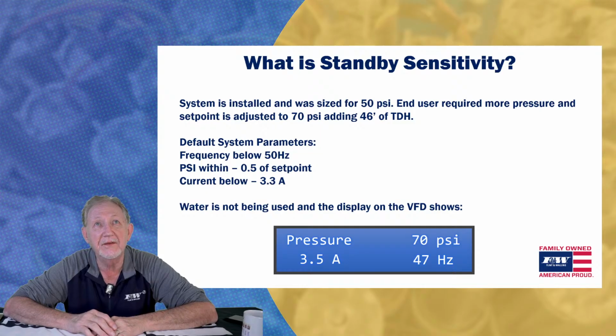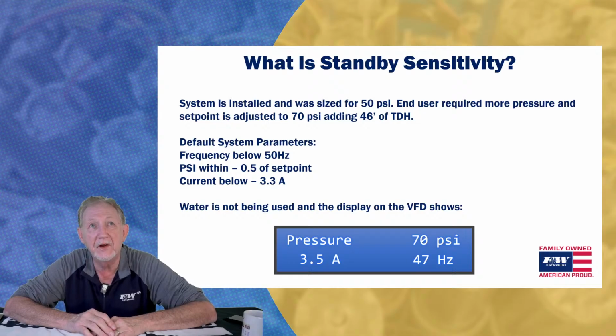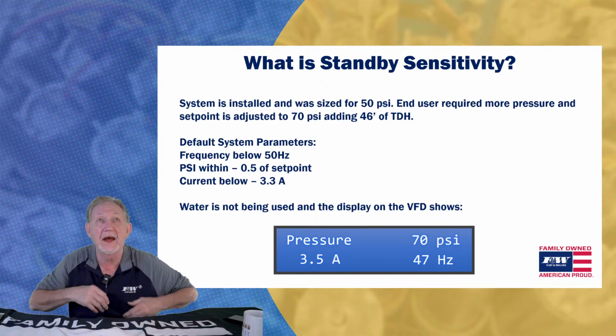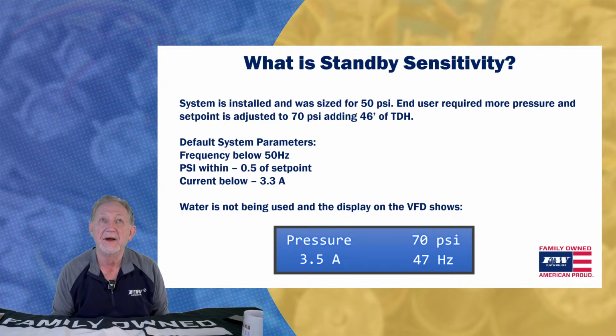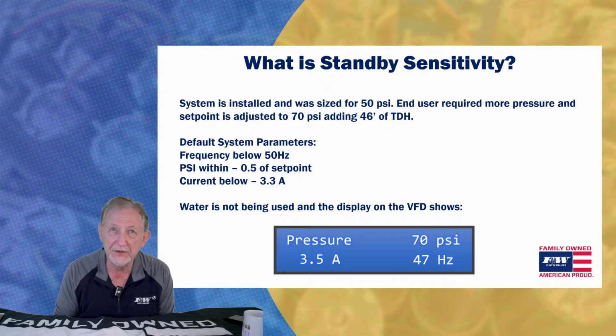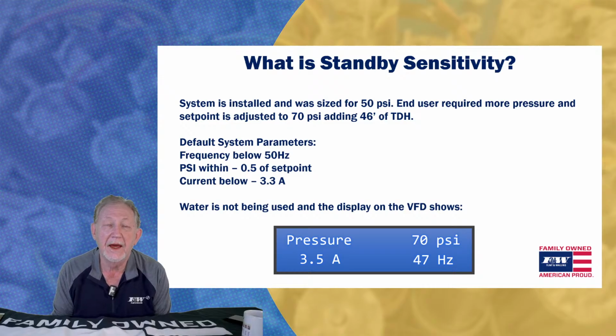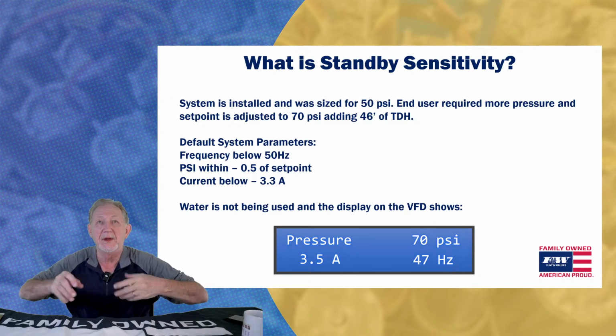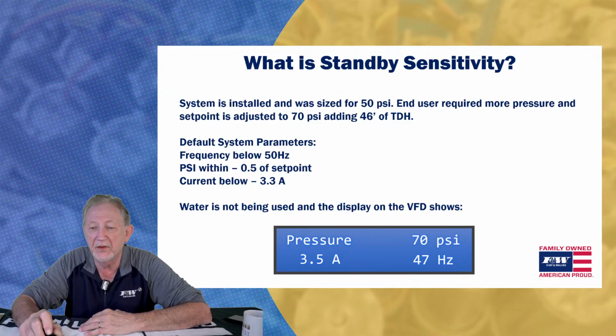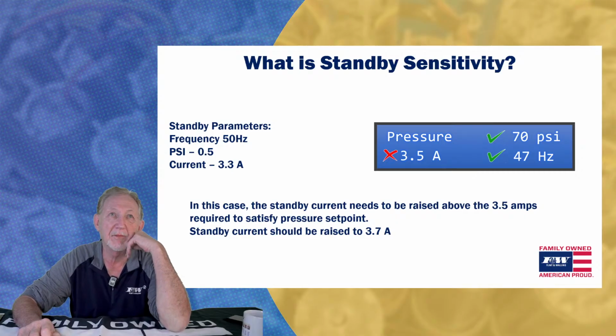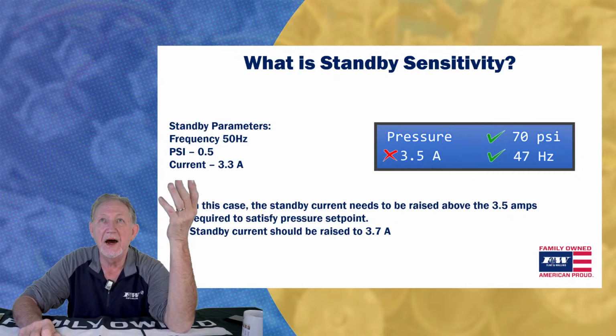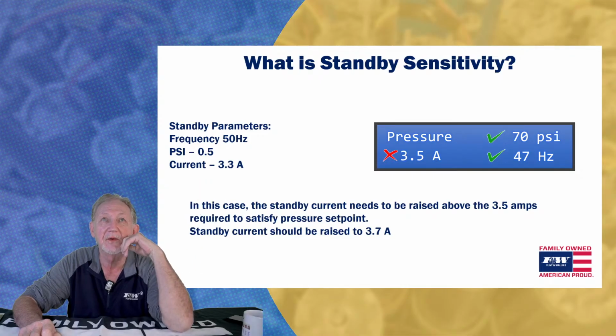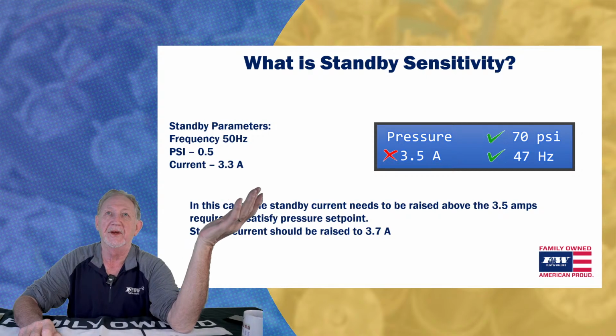So what happens? You've got the drive set at 50 hertz. The default parameters are going to be at 50 hertz. The set point's going to be within a half a pound of that pressure, that 70 PSI, and the current is going to have to be below that 3.3 amps. Well, here's what's happening. No water's being used, but look at what your drive's displaying. It's displaying that 50, it's displaying that 70, and it's displaying that 47, but that 3.5 amps is where the problem's at, because it's running higher than the threshold.